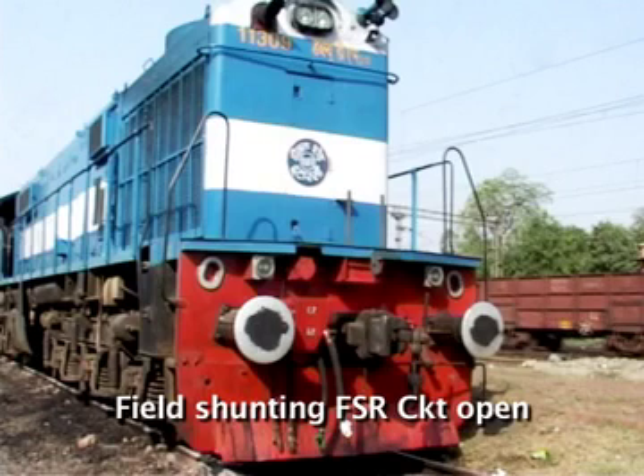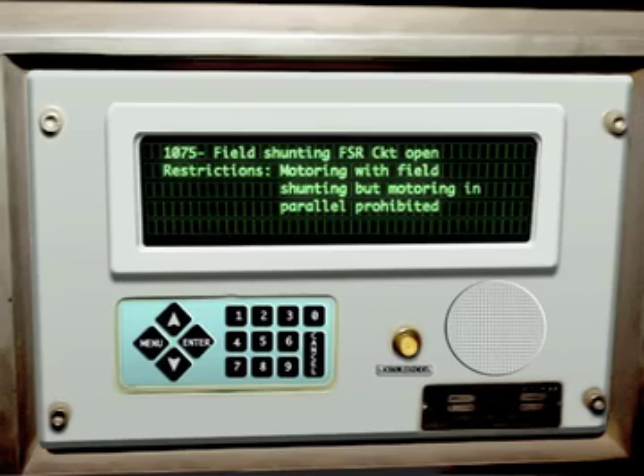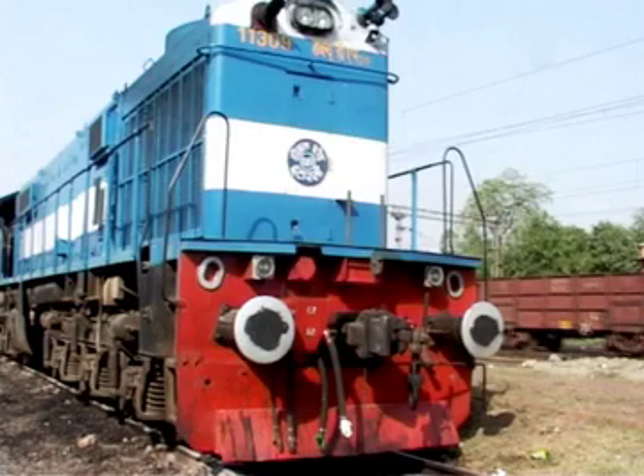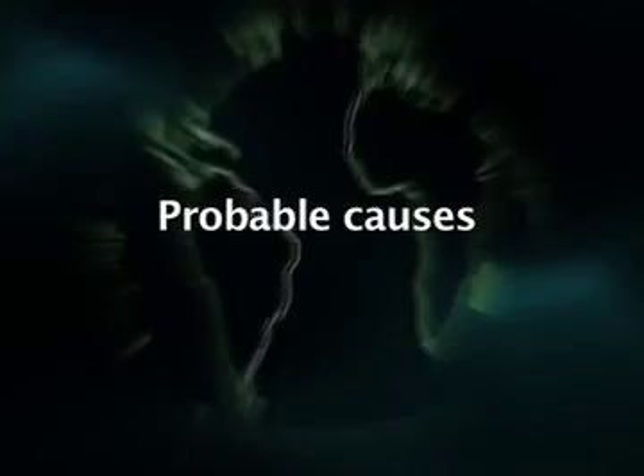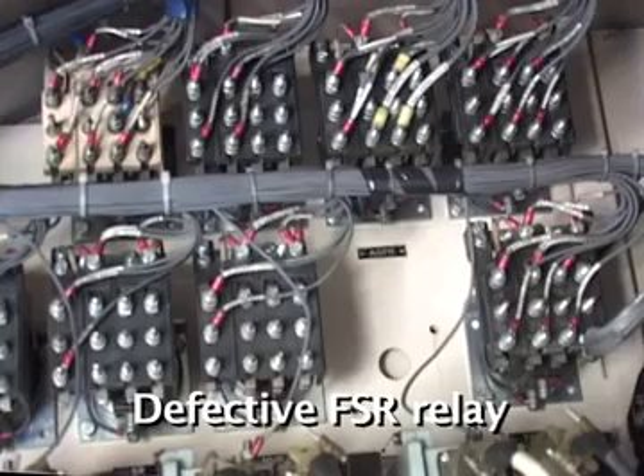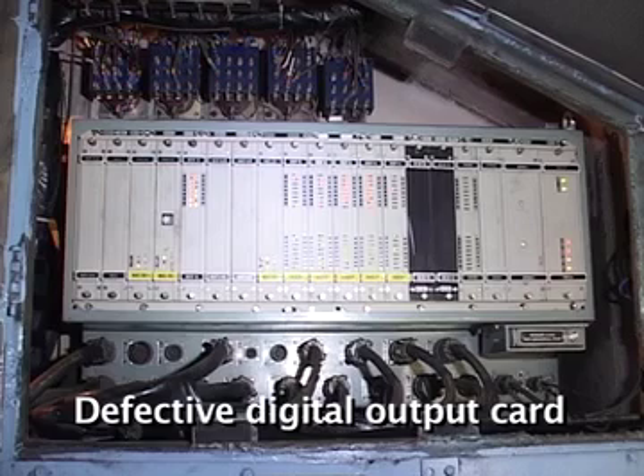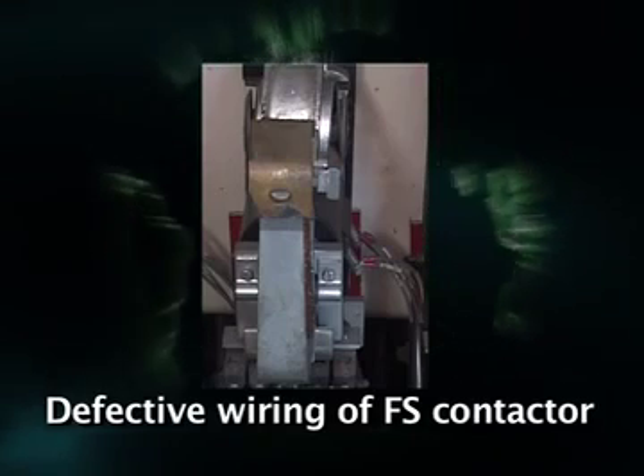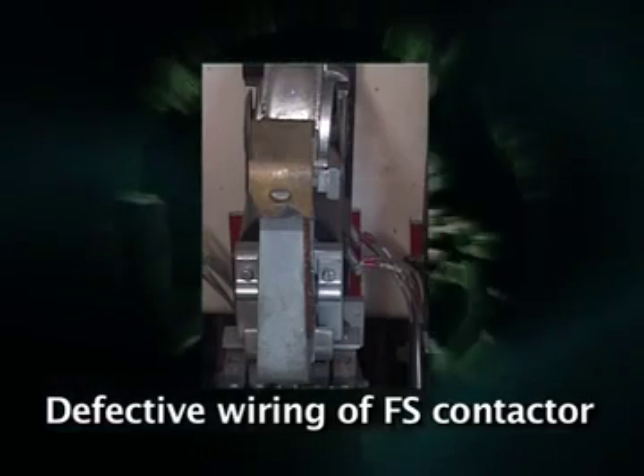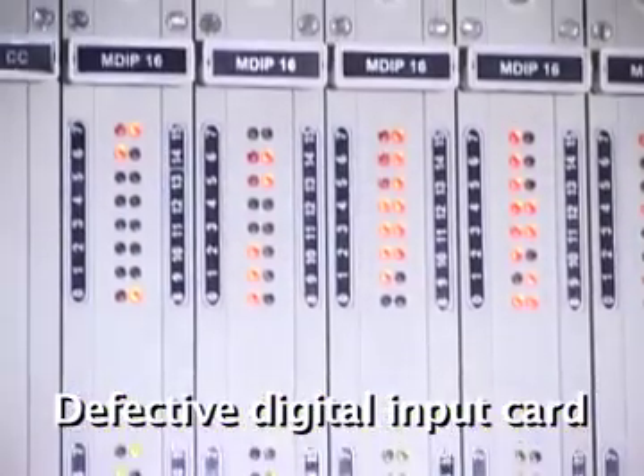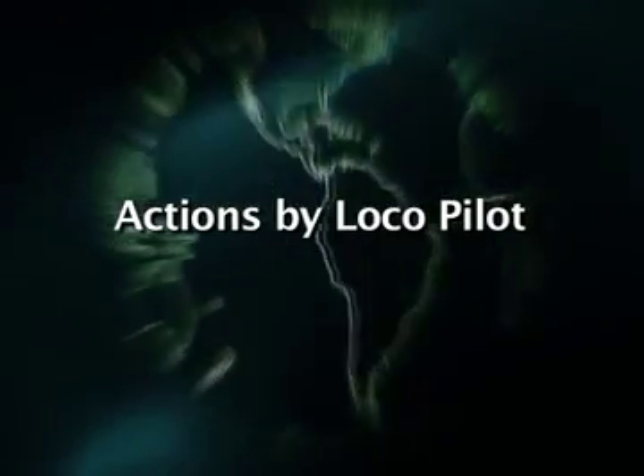Fault message coming. Field shunting FSR CKT open. Message code 1075. Restriction: motoring with field shunting but motoring in parallel prohibited. Alarm bell ringing continuously for 30 seconds. Driver acknowledging fault. Probable causes: defective FSR relay, defective digital output card, defective wiring of FS contactor feedback, defective digital input card.